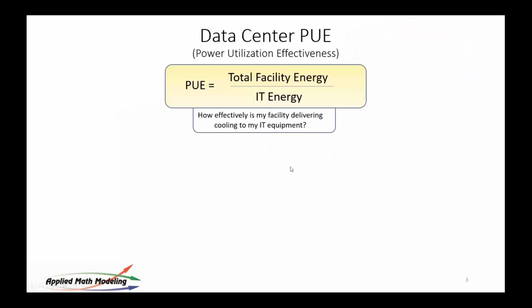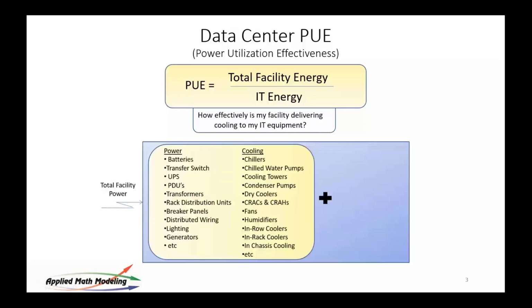Okay. So I want to just do a level set first. The audience is fairly diverse here, so I'm going to just back up and do a level set. PUE, I've done a lot of this before. I try not to be repetitive, so please bear with me. Power utilization effectiveness. It is total facility energy divided by IT energy. It was originally intended to be a representation of how effectively the IT is being cooled, how effective the facility is at cooling that IT equipment. Total facility power is made up of all the power, including cooling plus IT. That's the numerator. The denominator is just IT power.